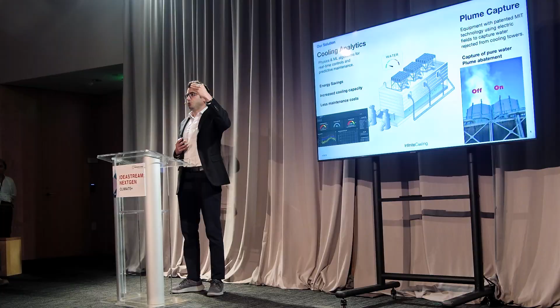So these products are already engineered and already deployed, so I'll show you a couple of case studies. This is a natural gas power plant that we're working with in Wisconsin, over 600 megawatts. Initially, they contacted us because they had a water issue. They were already using treated recycled water as makeup for their cooling tower, but even with that, they didn't have enough water, and they had no idea how the cooling tower was affecting their performance. So we installed our TowerPulse solution.